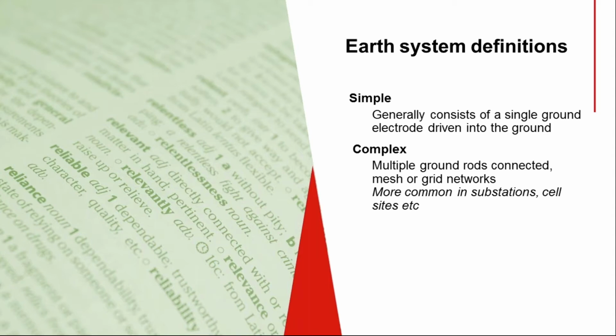with the one major caveat being, which we will see shortly, that a large electrode, a rectangular grid or something like that, can require a lot more room, a lot more space to perform the test. But the test itself is fundamentally the same as if you were just testing a single ground rod that is a building ground.